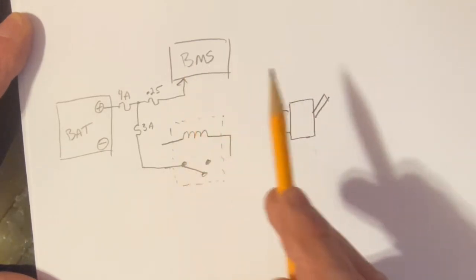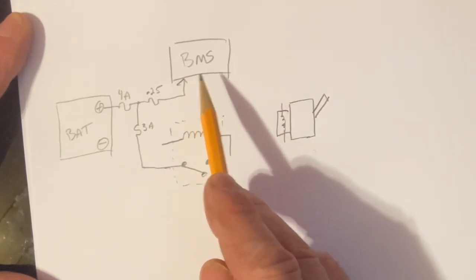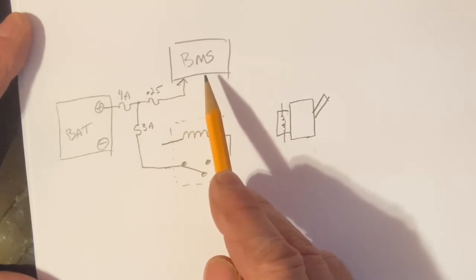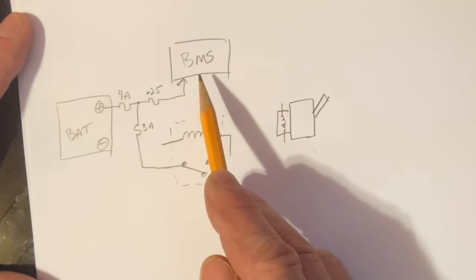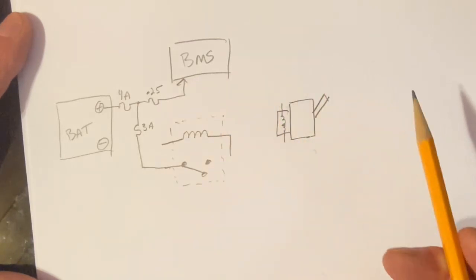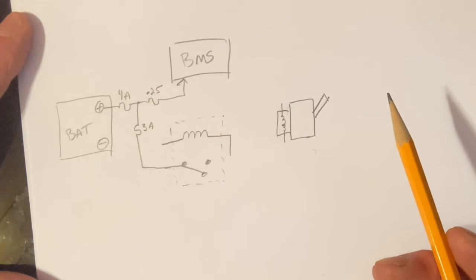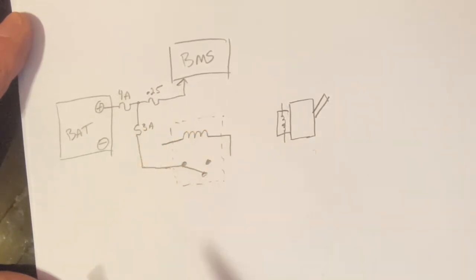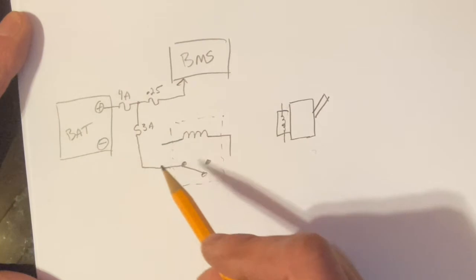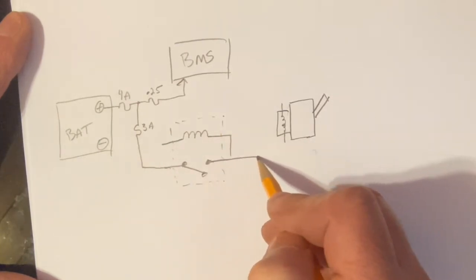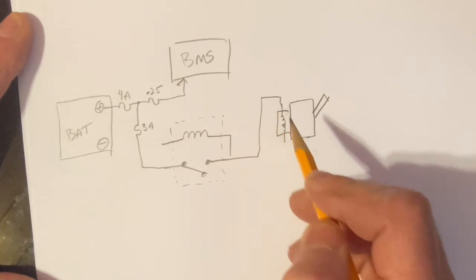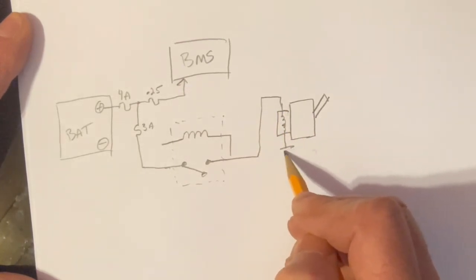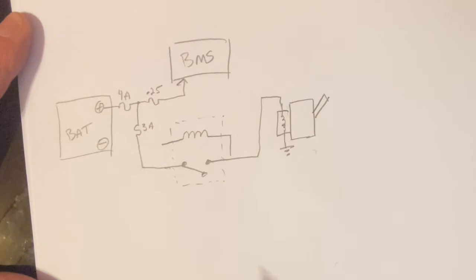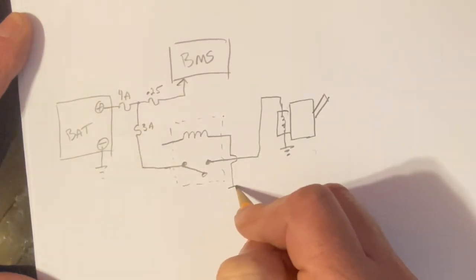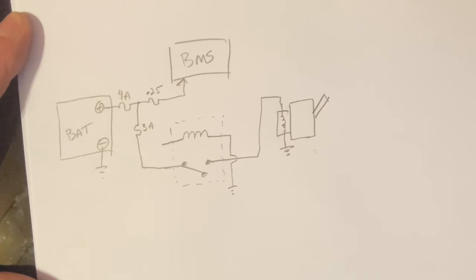The BMS is the sensor, and that has a very small low current relay inside of it. And those relays will activate based on the set points. So we've got power running everywhere that we need to. This 3 amp fuse ultimately protects the shunt coil. Now, just to simplify things, one side of everything goes to ground. Little jumper there. Okay, we've got all our grounds and our main power connected.